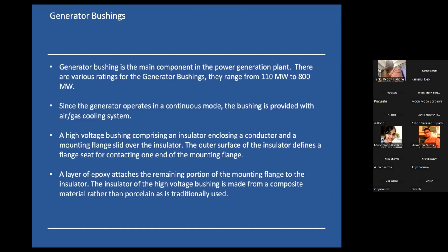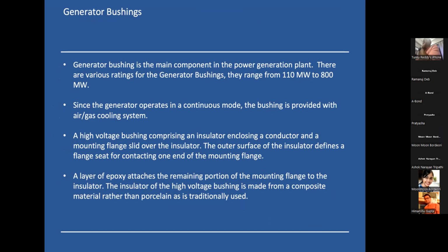Now, when it comes to generator bushings, it is the main component in the power generation plant. We manufacture various ranges of generator bushings. Our lowest range is 110 megawatt. An important feature of generator bushings is that they have to operate in a continuous mode, which is why they have to be provided with an air or gas cooling system.